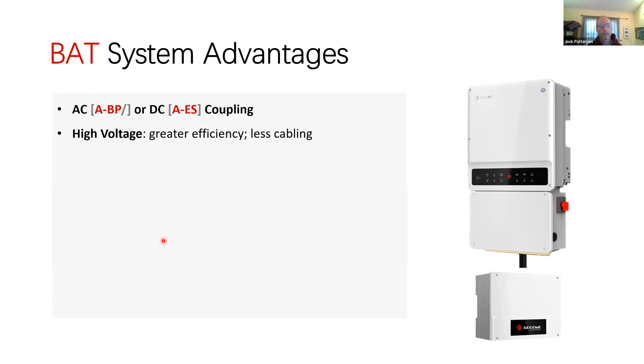Now you have a 60-foot run of wiring from the inverter to the basement. How are you going to do that with 3/0, 4/0 cable? It's much easier with number 6 and number 8 building wire. And that's what you can do when you have high voltage. You can just use the thinner wire. There's a great DC bus here, 50 amps. What does that actually mean? It means, bottom line, you can't think in terms of 48-volt systems. This is a high voltage system. So we're high voltage times that 50 amps. We're talking about a lot of power capability to move along here.